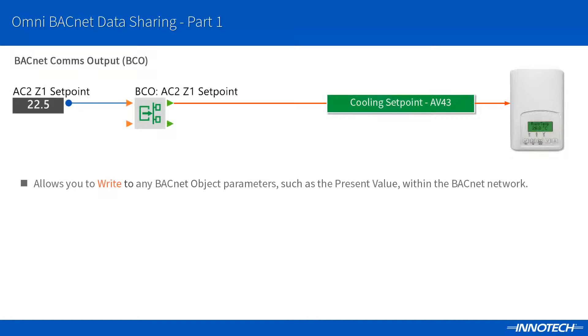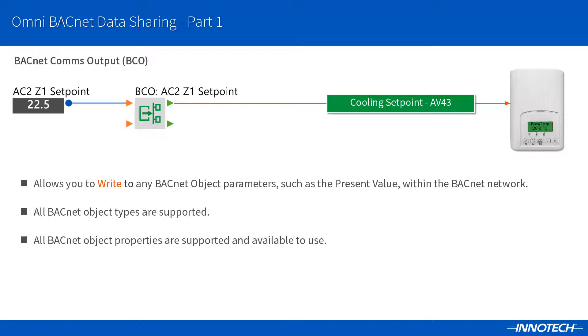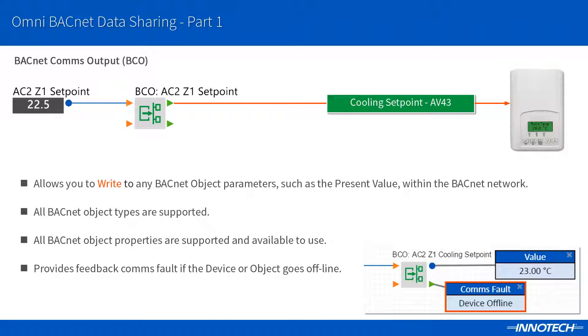The BCO block provides the ability to write to an object's property such as the present value. This could be a set point on a device or to override a binary output to control a fan on or off. As long as the remote object supports the right command, you can perform many tasks within the network. As with the BCI, there are many property types to select from as listed by the BACnet standards, and the most common property used is the object's present value. Comms fault feedback is also supported to advise if the remote object or device goes offline or has other issues. We will look at each of these blocks in more detail in part 2 and 3 of this series.